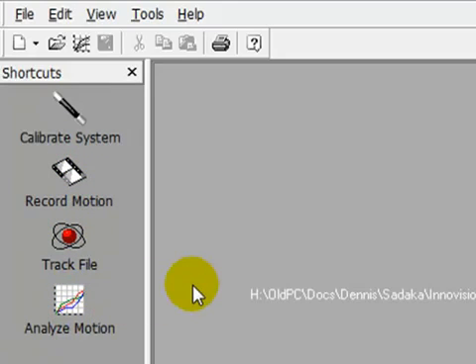Max Pro uses a dynamic wand calibration, which automatically includes linearization in its process.